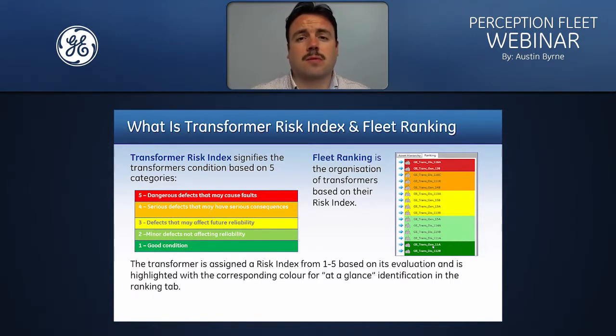As you can see from this table, we also color code the asset to make it easy to identify which category the transformer is in. On the right hand side, you can also see a representation of our fleet ranking table. Once the transformer is assigned a risk index, it is then shown in the fleet ranking based on its risk of failure. As you can see at the top of the table, we show assets that are most in danger of failing, right through to the bottom where the assets are seen to be operating as normal.